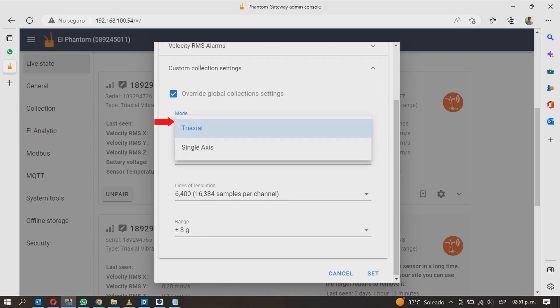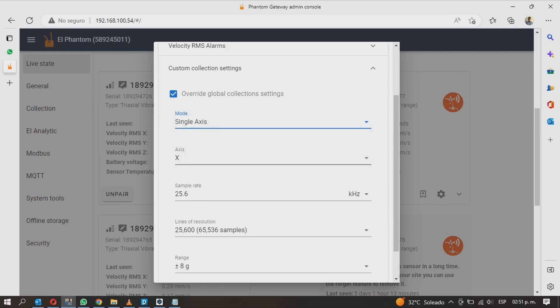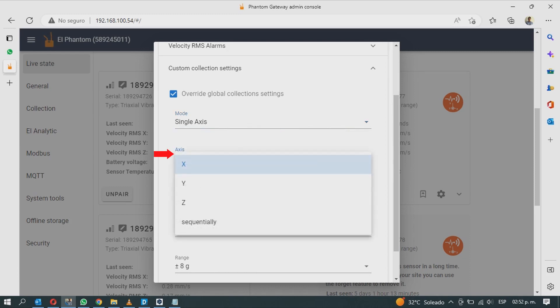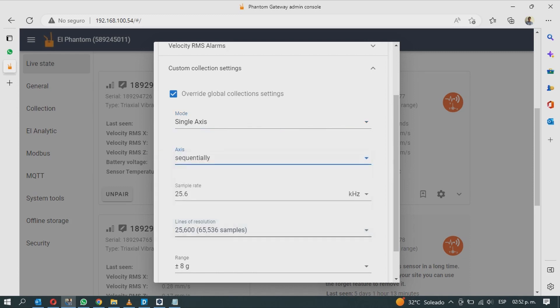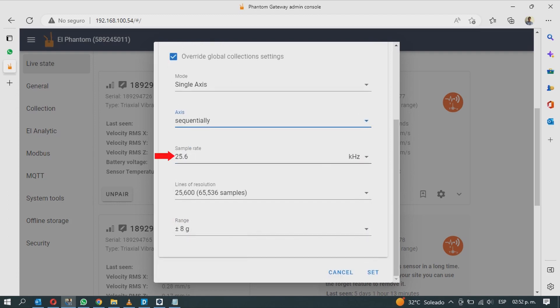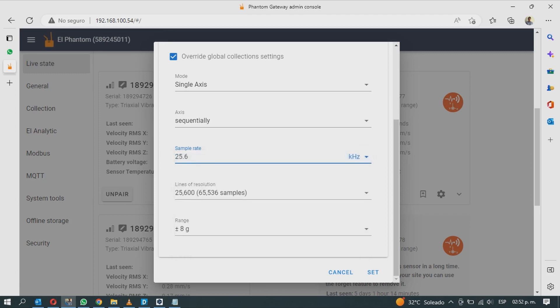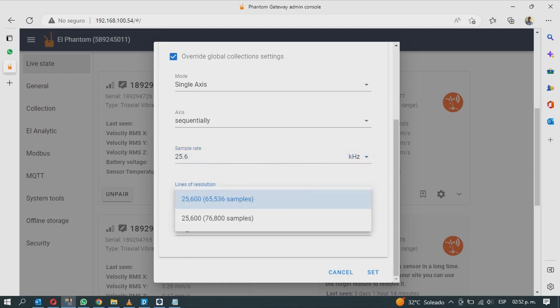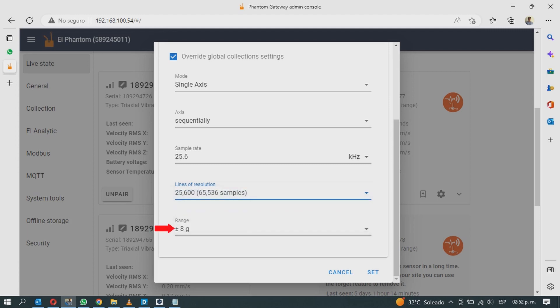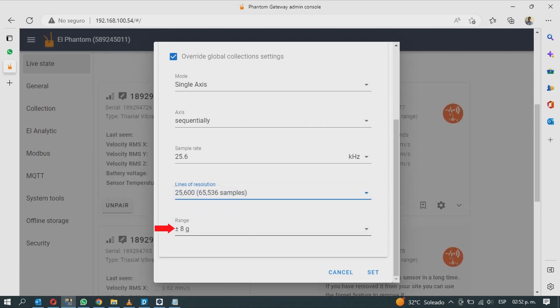You can choose to record data in triaxial or single axis mode. In single axis mode you can choose which axis to record or record all axes sequentially. You can also change the sample rate, the resolution lines, and the dynamic range whose options will depend on whether you have a high range or a low range sensor.